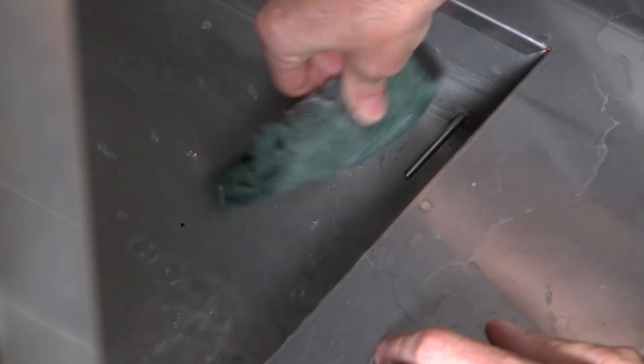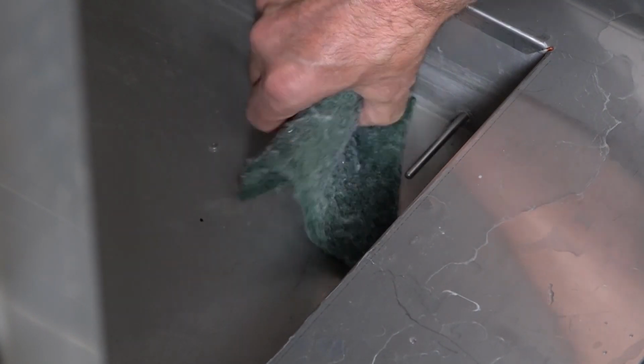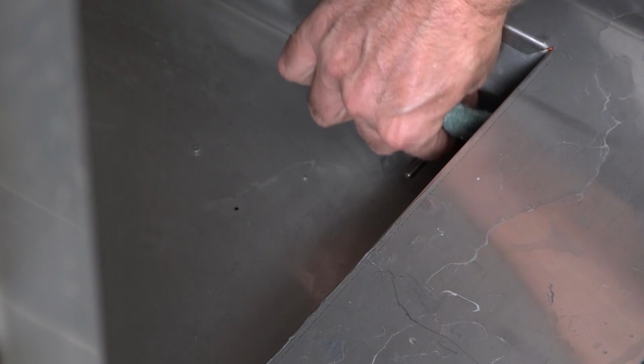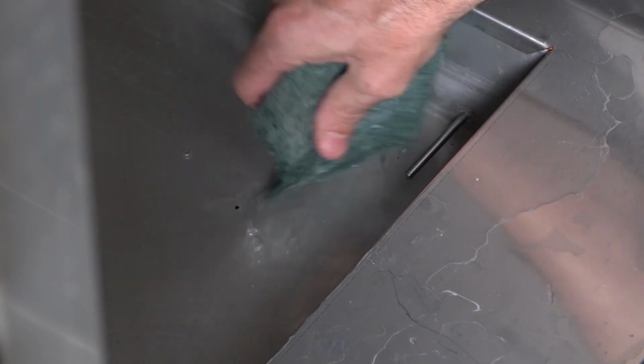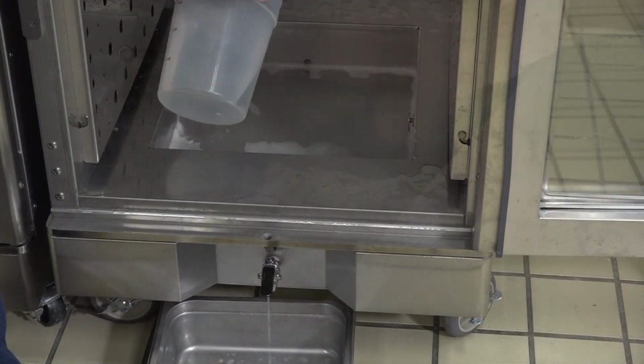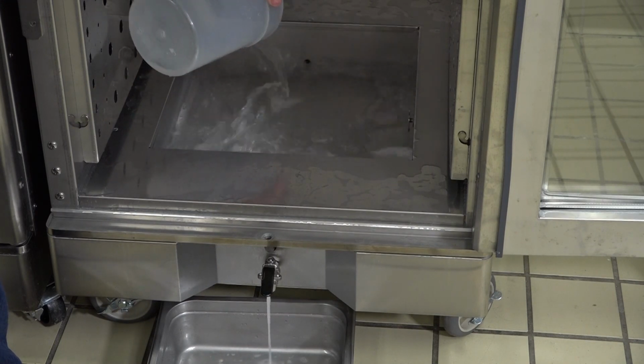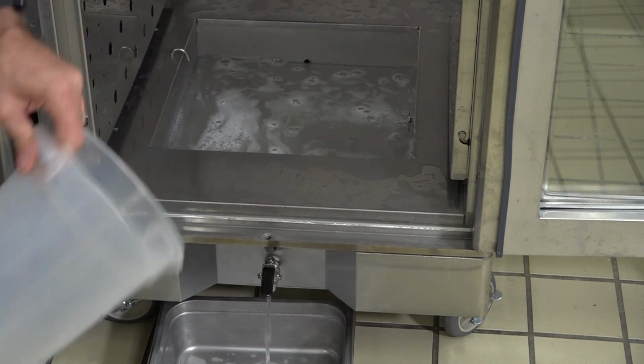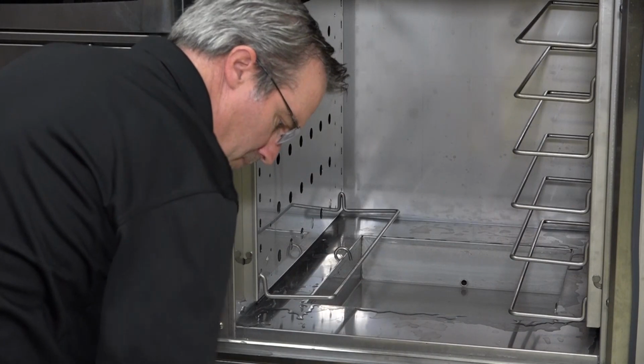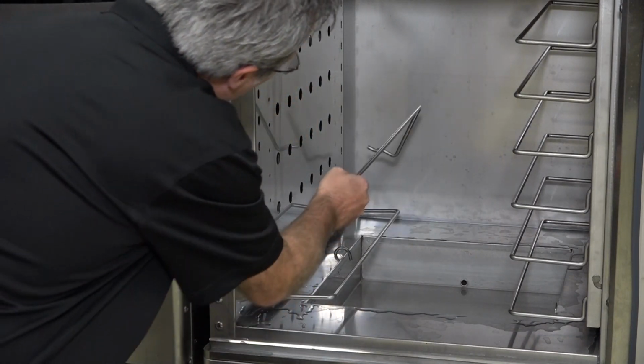Inspect for scale buildup on the tank surface, the water level sensor, and the water probe. If present, apply a descaling agent. Please read all warnings and follow directions listed on the descaling agent package. Rinse all inside surfaces including the evaporator and dry with a clean towel. Rinse and dry and replace the rack supports.